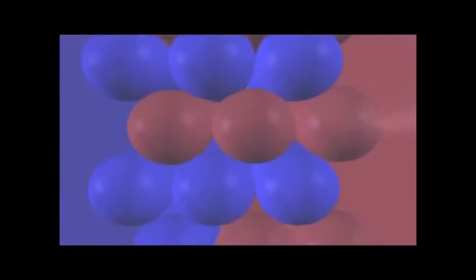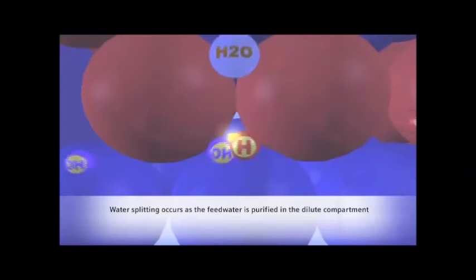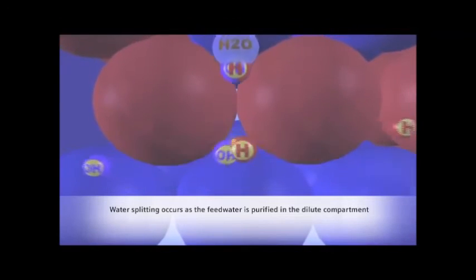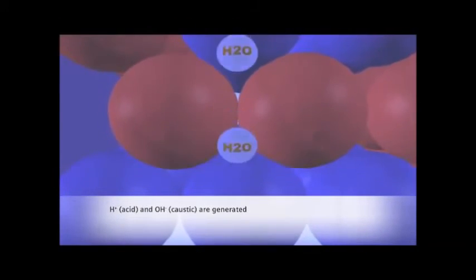At the lower end of the purification compartments, where the ion concentration has been reduced to the parts per trillion level, the electric field becomes concentrated between the resin beads and the surrounding water. When this localized voltage potential exceeds approximately eight-tenths of a volt, an electrochemical reaction occurs and water molecules are split into hydrogen and hydroxide ions, which are essentially acid and caustic.